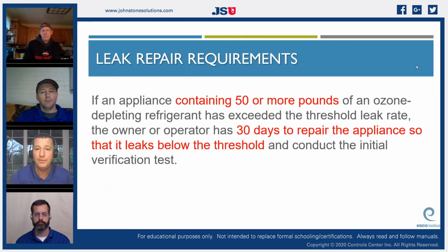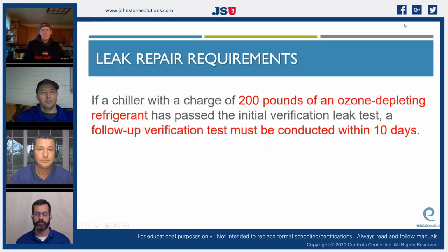If an appliance containing 50 or more pounds of an ozone depleting refrigerant, remember what's ozone depleting? Chlorine, if it's a chlorinated, a CFC, HCFC, has exceeded the threshold leak rate, the owner or operator has 30 days to repair the appliance so that it leaks below the threshold. 30 days. If that's got R22 in it, R410A in it, 30 days. That's why so many people are going to CO2. It's exempt. If I have a leak on a CO2 system, I just go buy some more CO2.